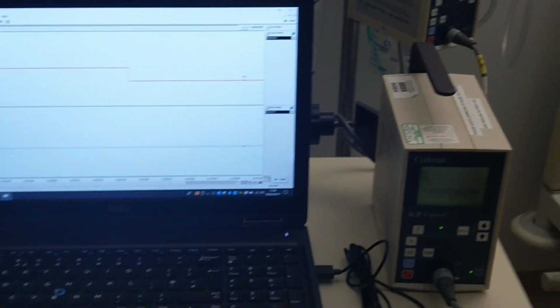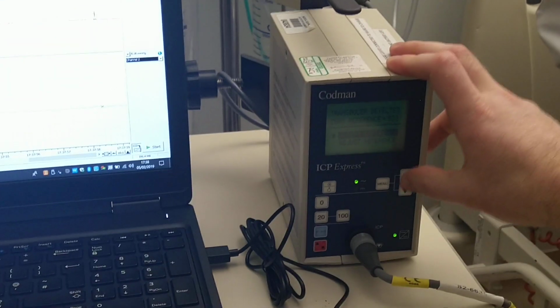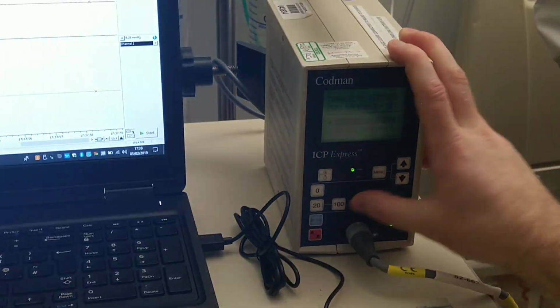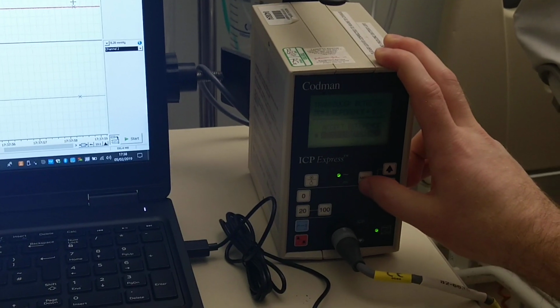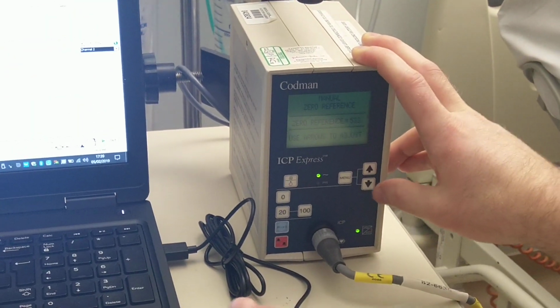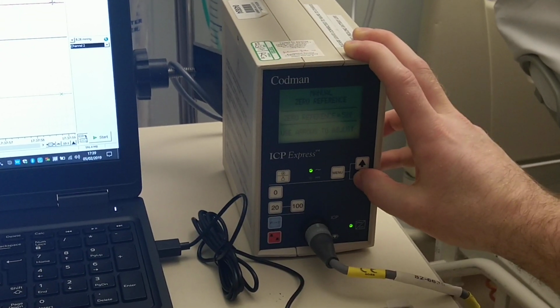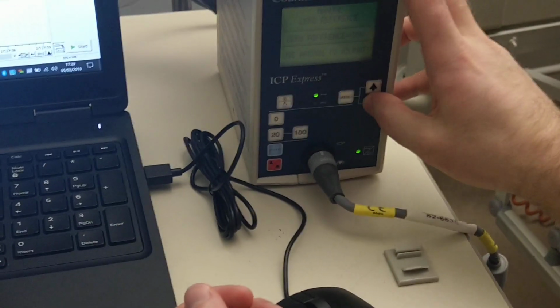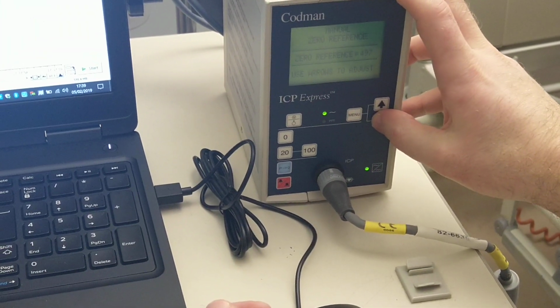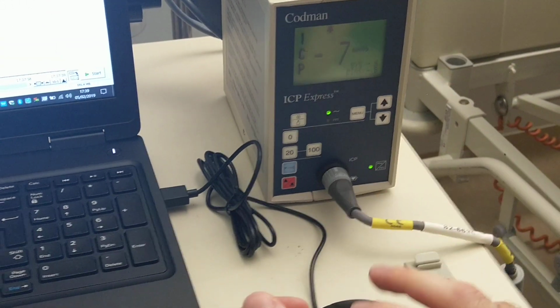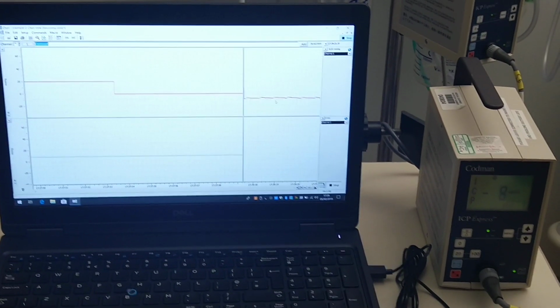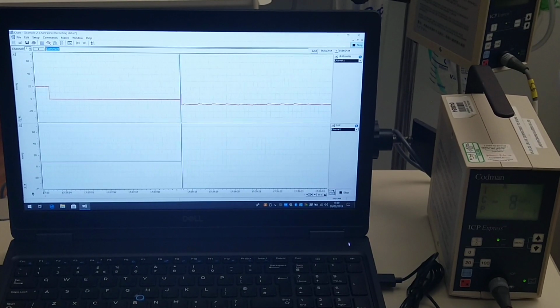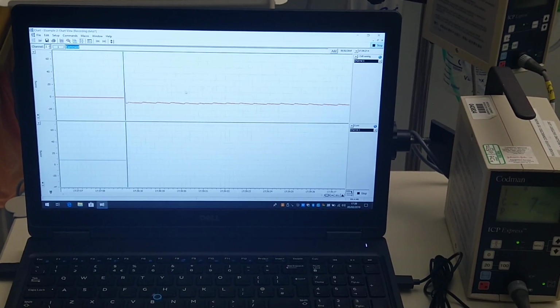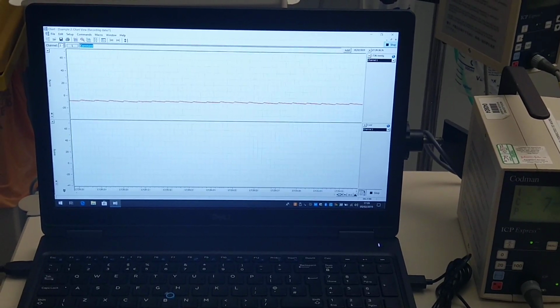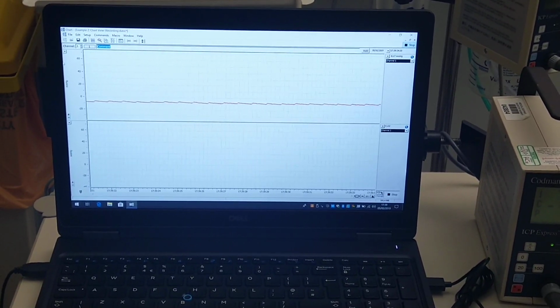This is very important. There's a reference number on the computer clip and recorded from the time of insertion on the ICP transducer wire. So I need to make sure that the correct reference number is entered now. So adjust reference. You can normally find it in the operation notes or written on the transducer cable. So I'm going to move that down to 497. Okay, 497, press menu, and you can see we've got an ICP number there, and if I press start here, I should now see a trace, and I can see a trace. I'm going to leave that as it currently is. You can see it's recording, so I'll press save, and then we can just leave that plugged in overnight.